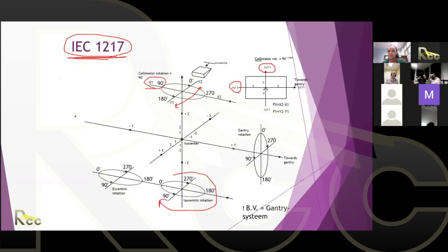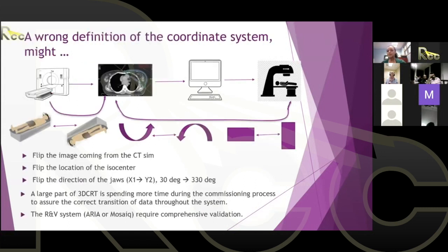So you just have to be careful as a physicist when you put a maintenance call to the engineer, which direction you're talking about. Now let's assume at the beginning you have the new linear accelerator, a CT simulator, and a planning system. You have to make sure that when you're doing the acceptance testing, you're going from one coordinate system to the other correctly.